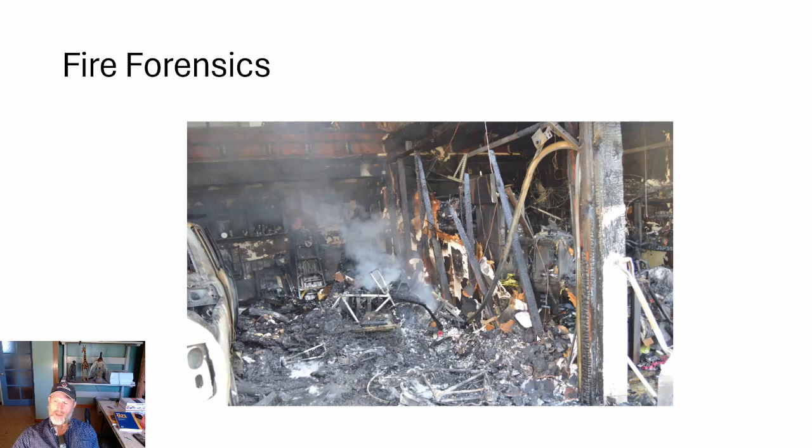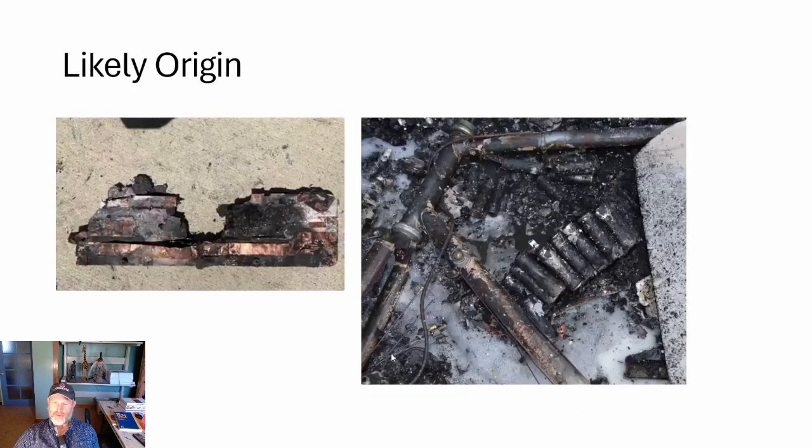Now, coupling two things, this charring effect here and the coloration and fire damage, complete destruction here, it would lead someone to think that there was a greater heat flux in this vicinity. And you can understand just how hard it is to try to put things together after flashover conditions. But further investigation at this location found this bicycle with a series of lithium ion batteries.